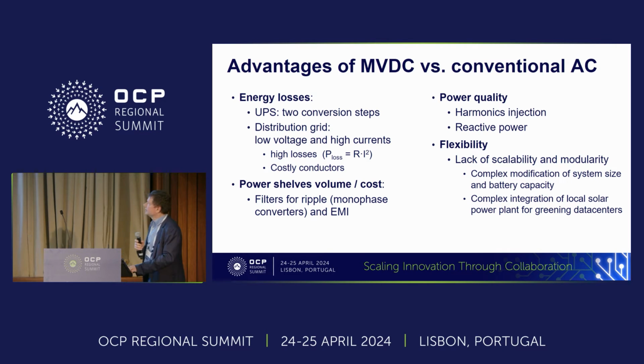Yes, and the other point is, of course, the power shelves themselves. The power shelves themselves in the long term can be reduced in volume, because actually these power shelves, these are power supplies which are powered with AC monophase. And this means that there's always a current ripple which has to be reduced and minimized by capacitors. And these capacitors, they are an element of insecurity and failure, but also they take a lot of volume. So if these power shelves, they can be optimized for DC, they will reduce volume. So less filters, less volume, less costs, more reliability.